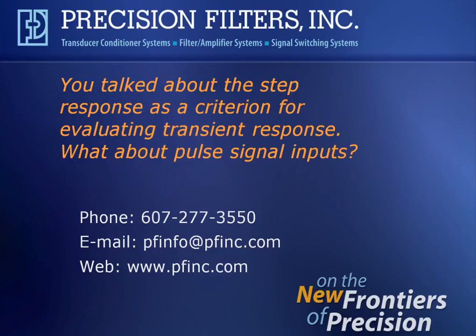Similarly, the location of the 3 dB frequency of the filter used in the measurement system can affect the measurement of the pulse. And a rule of thumb proposed by Patrick Walter would be that the pulse rise or fall time, whichever is smaller, typically these pulses have asymmetrical rise and fall times, but whichever is smaller times the 3 dB frequency, that should be greater than 0.45 to faithfully reproduce the pulse.